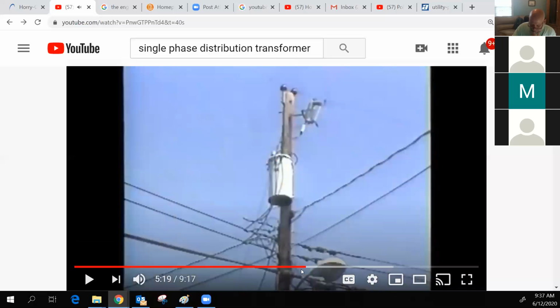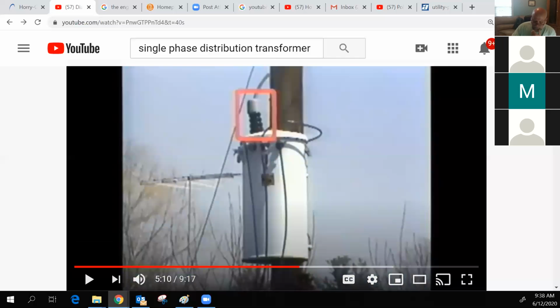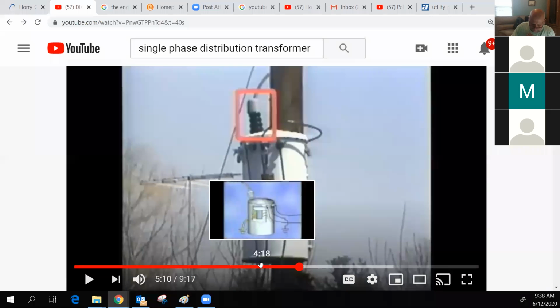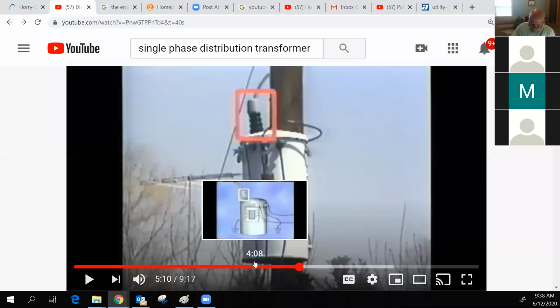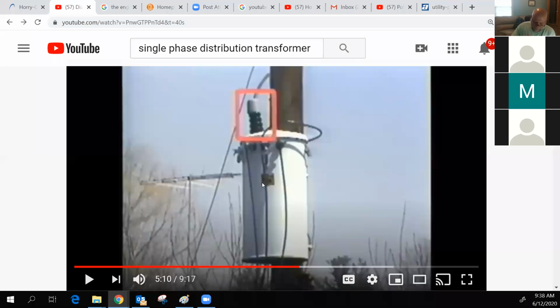Let me back that up one second to that picture, guys. I'm just going to point out a little something to you here. On this picture, if you can see my cursor, on the secondary side right here, it is what he talked about being grounded in the previous slide. And right there, you can see in that little picture it is grounded. At Duke, this is the way we used to ground the neutral bushing. We would take it out of the top and go back around and ground it back to the system neutral. Well, they've actually done away with this and come out of the bottom.